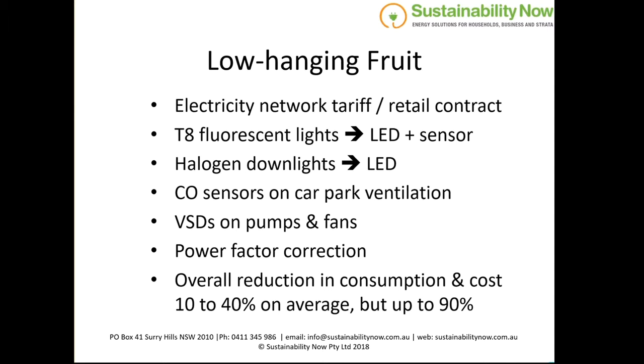So coupling that with variable speed drives on there, so that when the fans do engage, they only engage at a low speed, just the minimum necessary to clear the air and then move on. So again, variable speed drives on pumps and fans that don't need to run at full speed all the time. With centrifugal fans and pumps, it's not a linear relationship between speed and power. So reducing the speed of that motor that's controlling that pump or fan by 20% could result in a 50% electricity saving. So that's a really easy one.